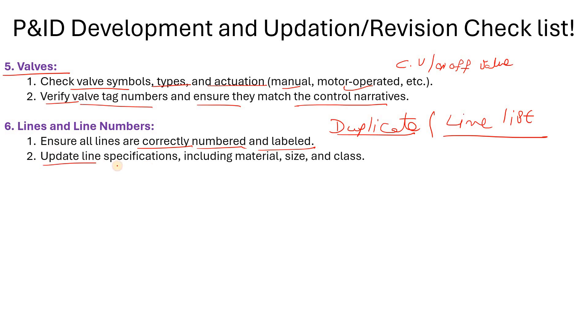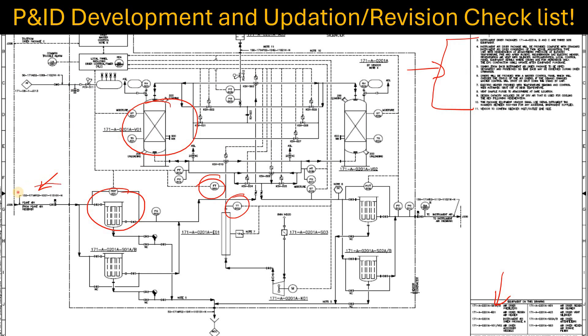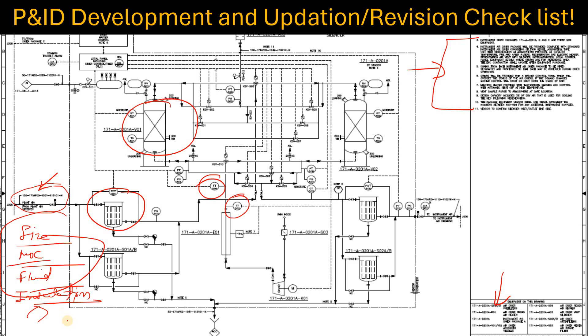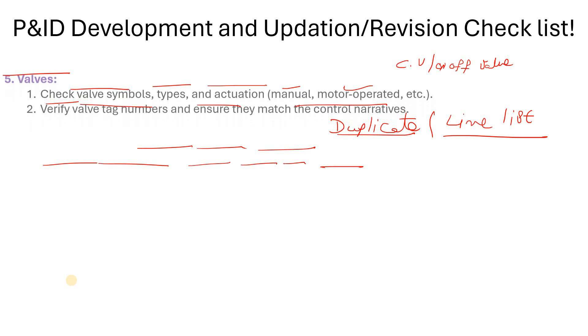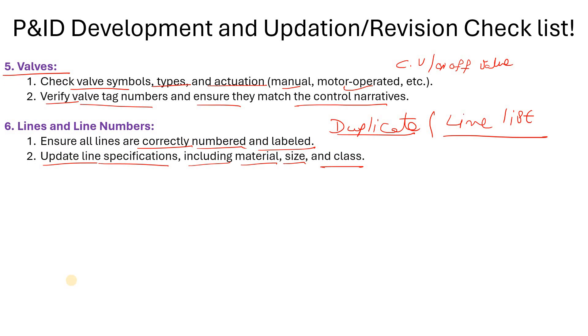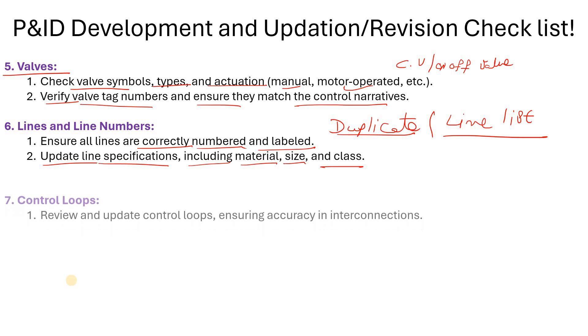Update your line specifications including materials, size, and class. In the line number you will find the size, class, MOC (material of construction), fluid, insulation specification, and insulation sizes. You must have an understanding of how to read the P&ID line number. If you have any difficulties with that, I have already prepared a video about it — you can check that out.